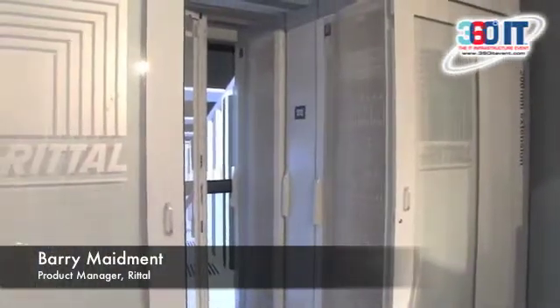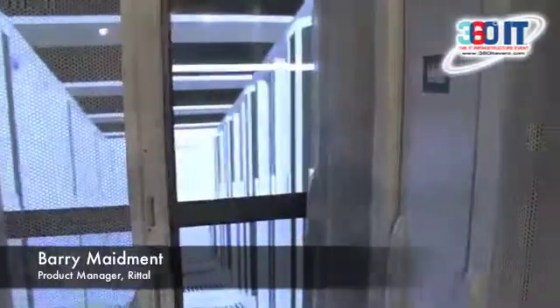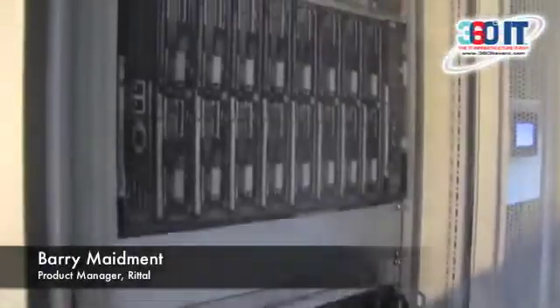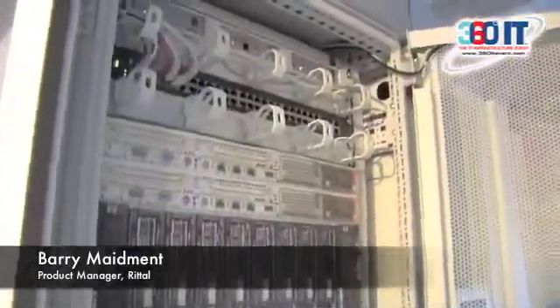Now what we're showing here is actually a cold aisle containment system. Cold aisle containment effectively takes the traditional model of hot aisle and cold aisle and makes it a lot more efficient. In the actual cold aisle containment, we put roof panels across the top, and we put doors on the end of the aisle, and what that effectively does is trap the air in front of the server and create a reservoir of air to allow the server to breathe, and then it exhausts the actual hot air from the actual return.